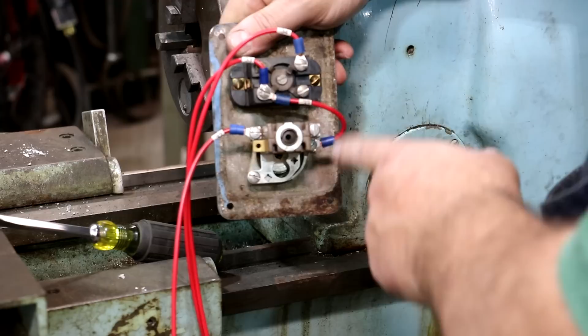The way this works is you have power coming in on wire 34, to this terminal. Whenever we push this button in, it shorts out across these terminals. The power goes through here, down through this bottom switch, and through here because this is normally closed. This goes to the coil.